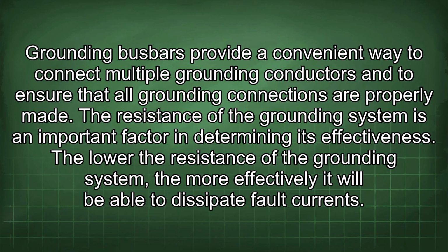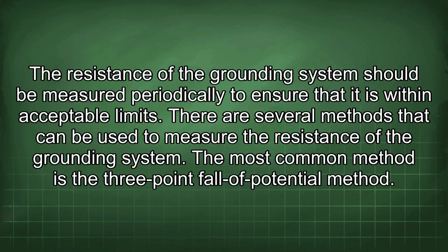connections are properly made. The resistance of the grounding system is an important factor in determining its effectiveness. The lower the resistance of the grounding system, the more effectively it will be able to dissipate fault currents. The resistance of the grounding system should be measured periodically to ensure that it is within acceptable limits. There are several methods that can be used to measure the resistance of the grounding system. The most common method is the 3-point fall of potential method.